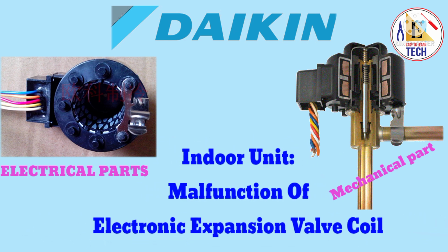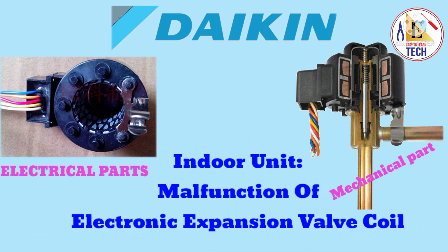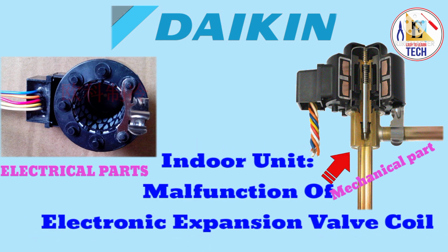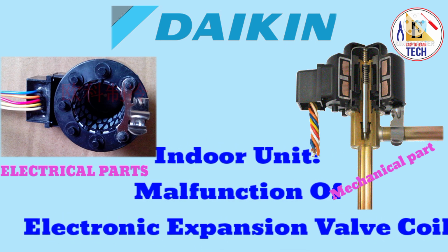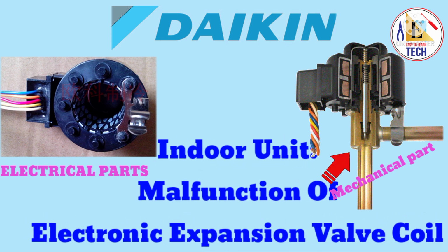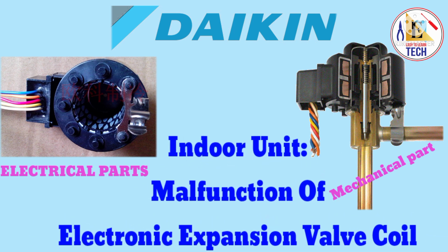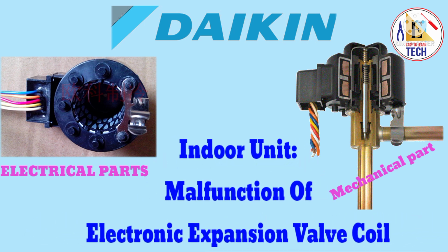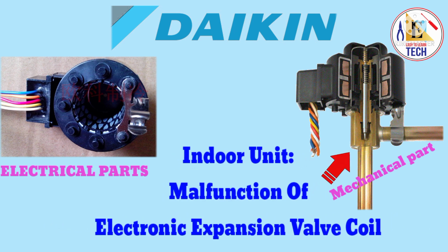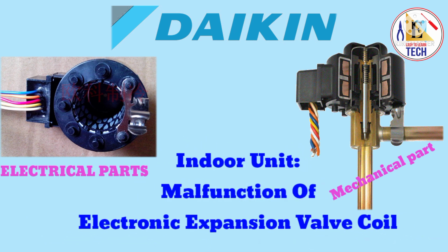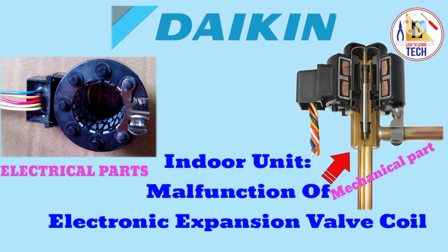To solve this problem, first of all you have to check the electrical part of your electronic expansion valve. If your electrical part is gone, if the solenoid valve is gone, then you have to change it and you will get the solution for the error A9. After changing that, again if you are getting the same problem, then you have to change the mechanical part as well as the electrical part and you will get the solution for the error A9.